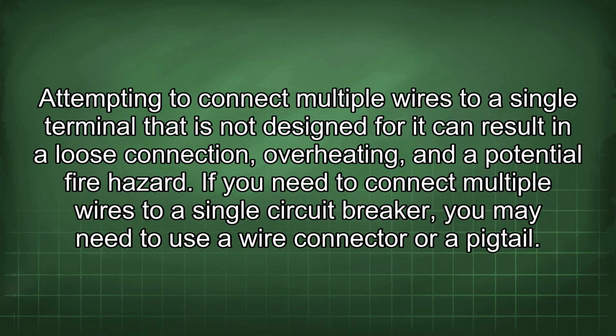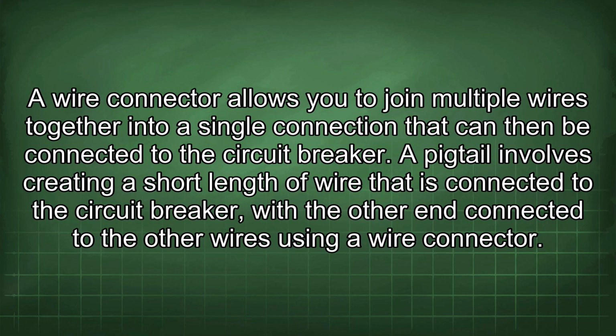Attempting to connect multiple wires to a single terminal that is not designed for it can result in a loose connection, overheating, and a potential fire hazard. If you need to connect multiple wires to a single circuit breaker, you may need to use a wire connector or a pigtail. A wire connector allows you to join multiple wires together into a single connection that can then be connected to the circuit breaker.